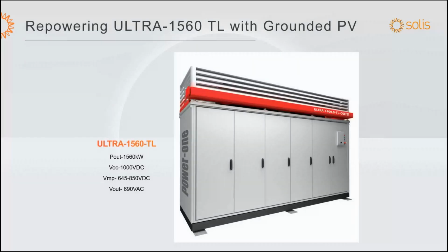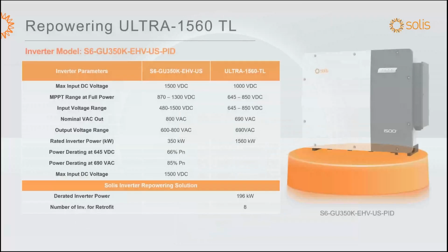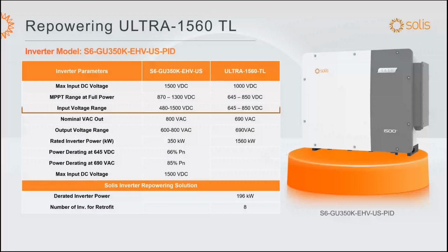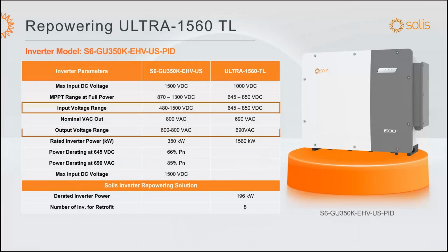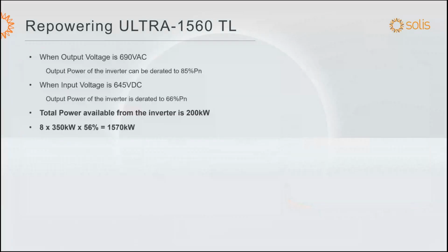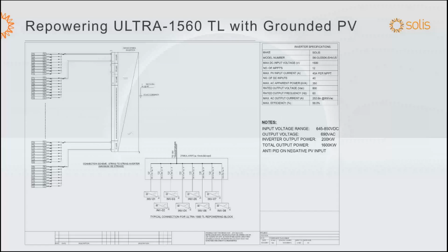Ultra 1560 grounded system, and how we can replace it with that inverter. The example is similar to before. The input voltage range is okay, the output voltage range is okay. It takes 8 inverters to replace it. And basically, the difference here is that it shows First Solar modules. So this is how you connect First Solar modules into each MPPT.